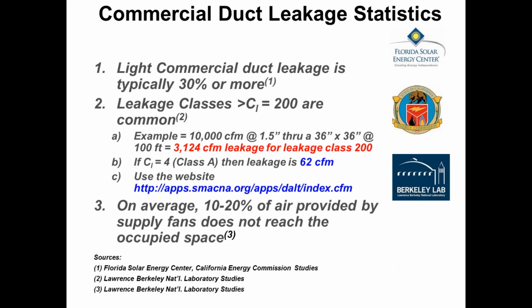If you guys are specifying systems and you specify the typical duct leakage class of 200, I'm not going to go through the math right now because of time, but that's about 3,000 CFM leakage on a 10,000 CFM system. If your leakage class in your specs is 200, you're basically saying I am okay with 30% of my outside air leaking. Generally, we suggest you target a class of 4, or class A system, which would mean in an example of 10,000 CFM, only 62 CFM would be allowed to leak. That would be pretty significant over the typical 30%.